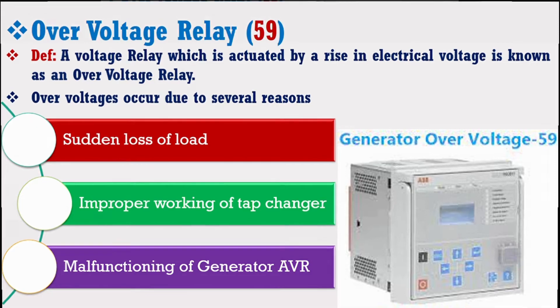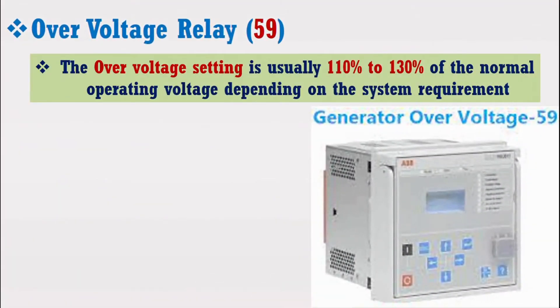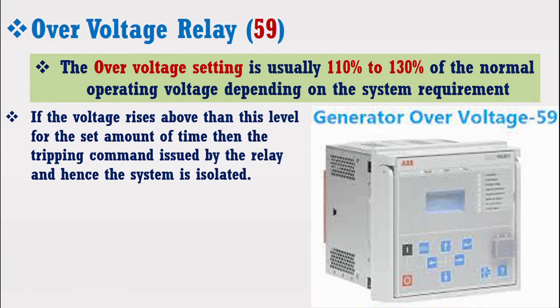The overvoltage setting is usually 110% to 130% of the normal operating voltage depending upon the system requirement. If the voltage rises above this level for the set amount of time, then the tripping command is issued by the relay and hence the system is isolated. Let's discuss its designing in MATLAB Simulink software.